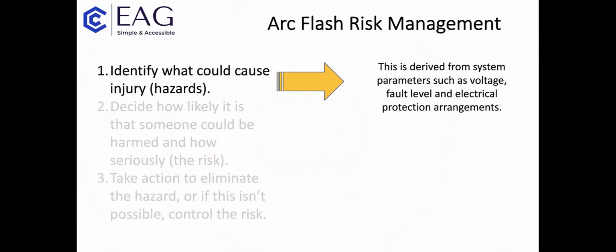You can see there's 3 principles of Arc Flash risk management. The first one's highlighted, and the second 2 are greyed out there. So at a basic level, we're asked to consider the 3 actions shown here. We're asked firstly to identify what could cause injury, in other words, hazards. When we look at arc flash, it's derived from system parameters such as voltage, such as fault level, and electrical protection arrangements.